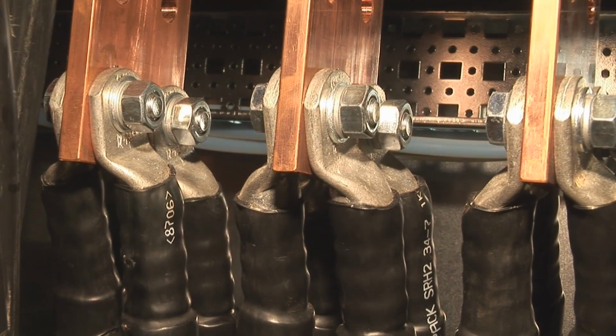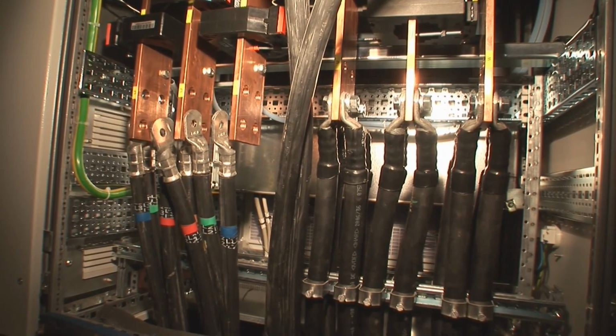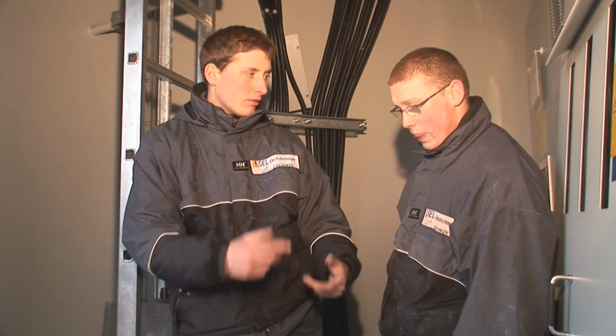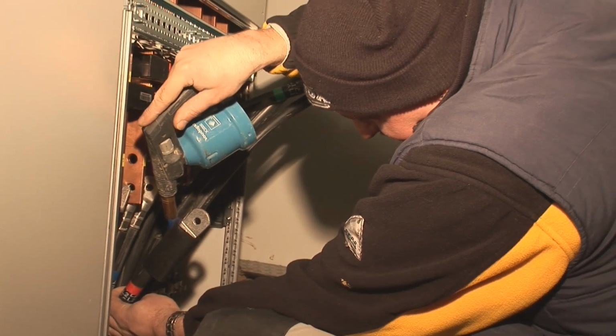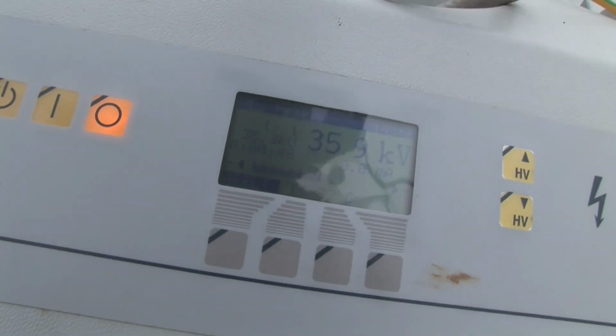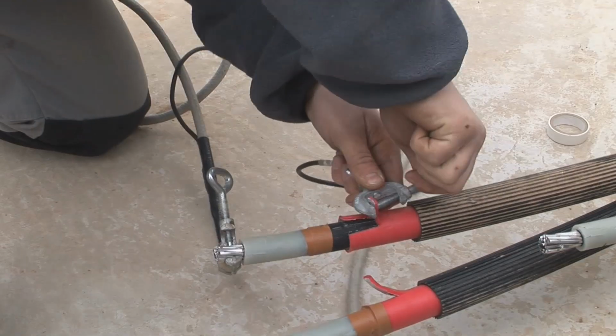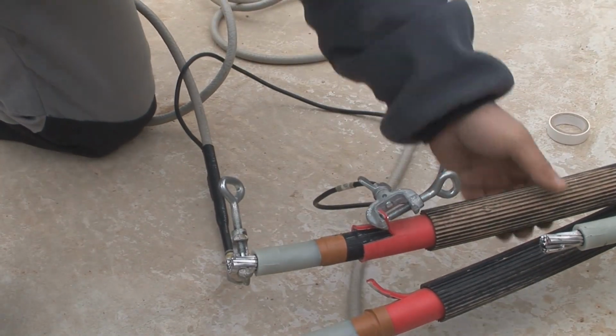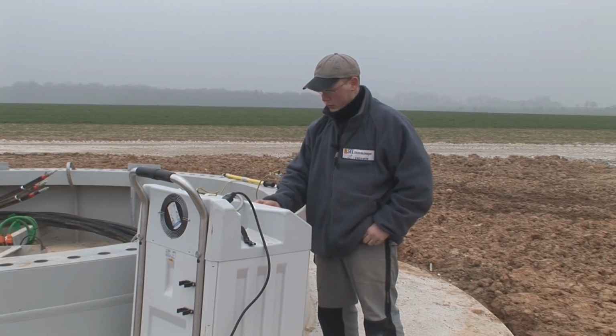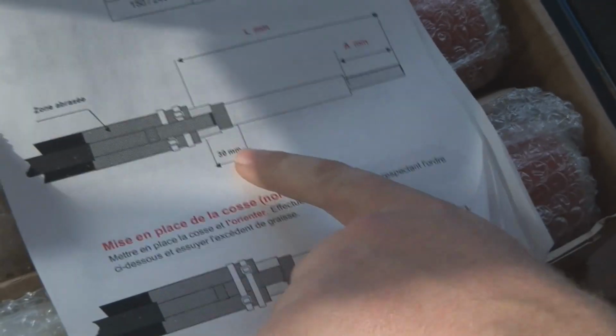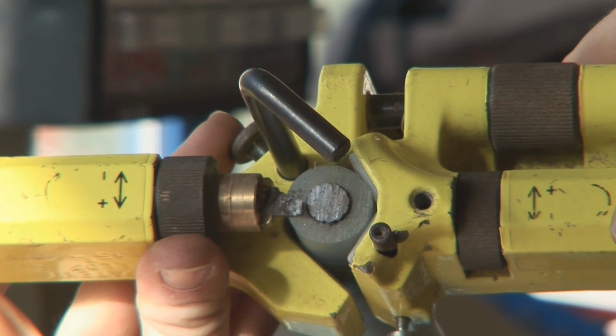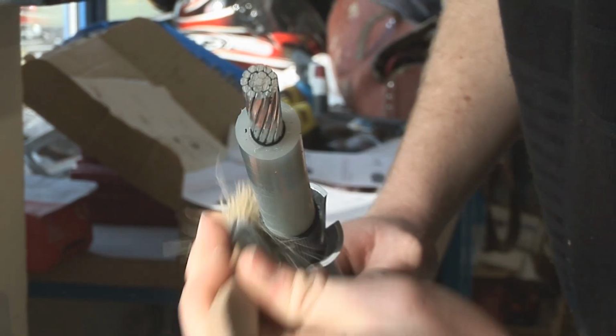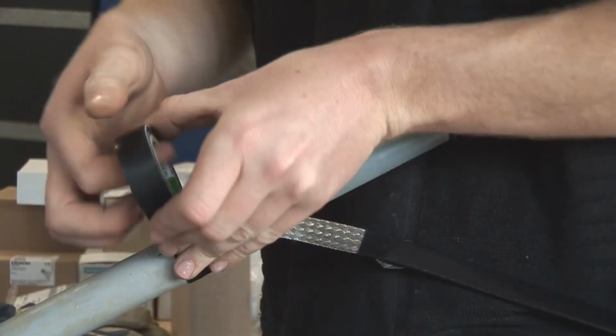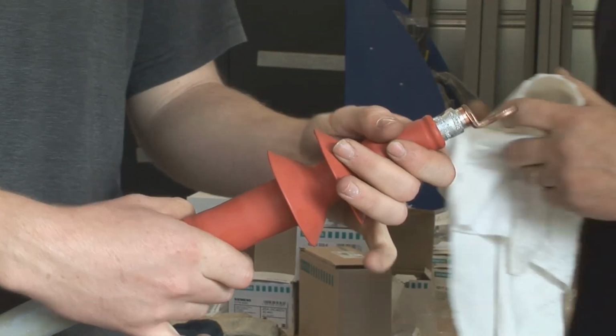Before connecting, we check the cables by testing them at very low frequency, up to 63 kilovolts. We test at three times the nominal grid voltage, for example 36,000 volts, to check there are no faults on the lines. If there are underground voltage boxes, we check they hold up well. Then we make the connectors, and once that's done, we run another test at 36,000 volts. Then we connect up the whole farm.